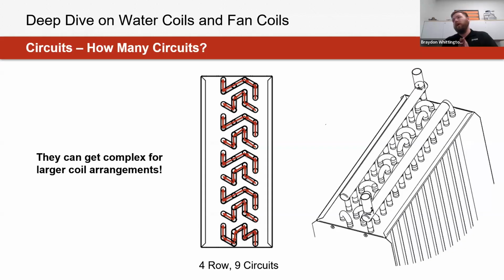But with that, it's also the trade-off of maybe the additional size that might add to the coil, or maybe not as unique, or more unique, sizes that might not pair with, say, a terminal or fan coil equipment, because we're more constrained and we look at what sizes we can actually play with when we're talking about, say, a 12 by 10 inch VAV product. There's only so much space in terms of how much we can intertwine those fluid passes that are going through there. So with that, that's why you might see a little bit more restrictions in terms of what that overall profile is going to look like from a circuitry perspective.